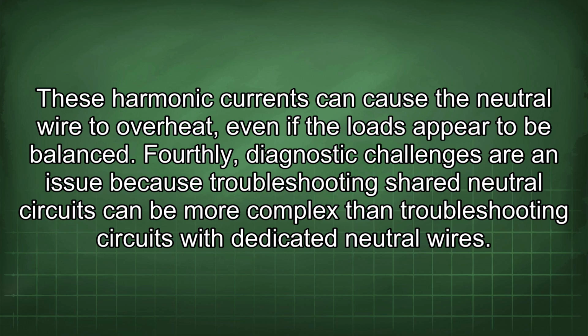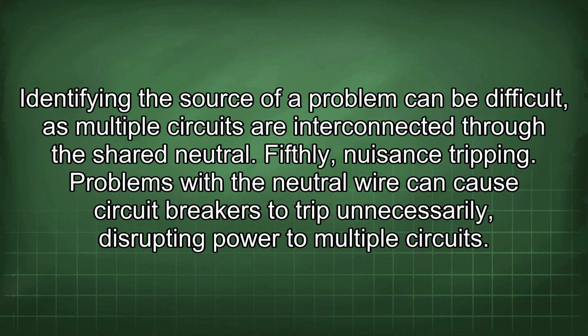Fourthly, diagnostic challenges are an issue because troubleshooting shared neutral circuits can be more complex than troubleshooting circuits with dedicated neutral wires. Identifying the source of a problem can be difficult, as multiple circuits are interconnected through the shared neutral. Fifthly, nuisance tripping. Problems with the neutral wire can cause circuit breakers to trip unnecessarily, disrupting power to multiple circuits.